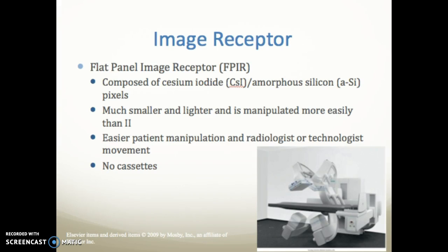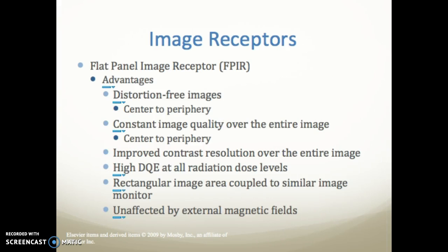The flat panel image receptor (FPIR) is composed of cesium iodide and amorphous silicon pixels. It is much smaller, lighter, and easier to manipulate than the II, making patient positioning easier for the radiologist or technologist, with no cassettes needed. Flat panel advantages include distortion-free images where the center and periphery are exactly the same, constant and improved contrast resolution over the entire image, high DQE at all dose levels, a rectangular image area compatible with a similar monitor, and it is unaffected by external magnetic fields.